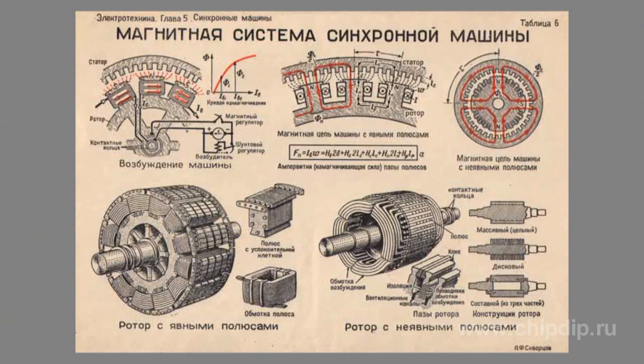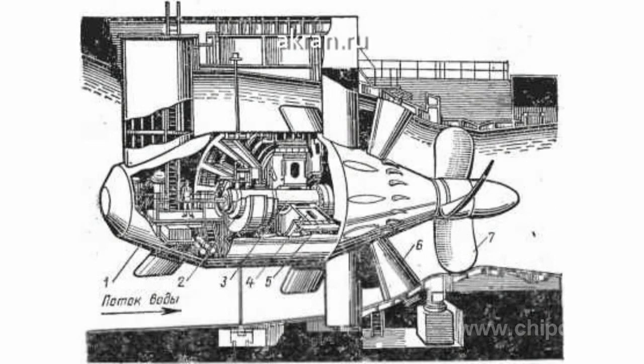The construction of a hydrogenerator is generally specified by the axle position of the rotor, rotational frequency, and turbine capacity. High-power slow hydrogenerators usually have a vertical axis of rotation, while high-speed ones are made with a horizontal axis of rotation.